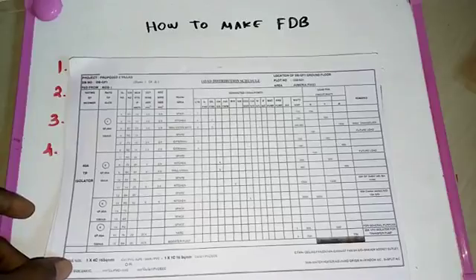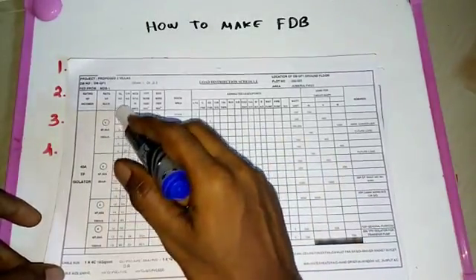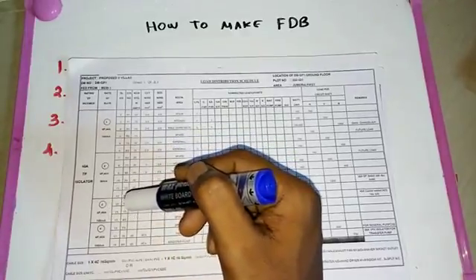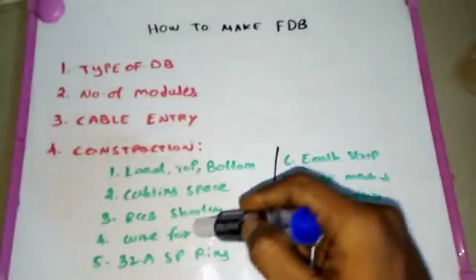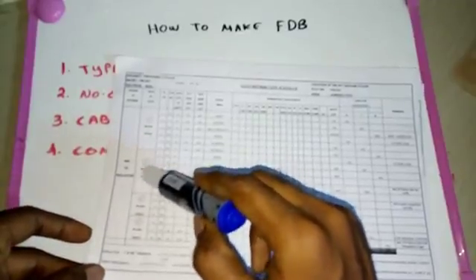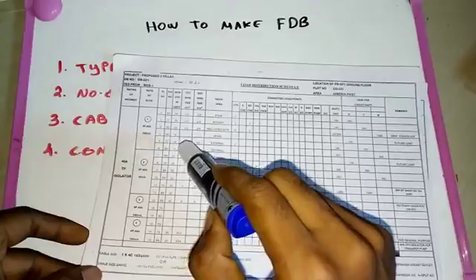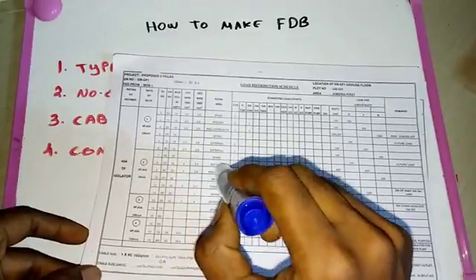For special DBs, we should not short more than three ELCBs together. Regarding wire size: if shorting more than two ELCBs, use a 16mm wire. If using a single ELCB, a 10mm wire is sufficient.